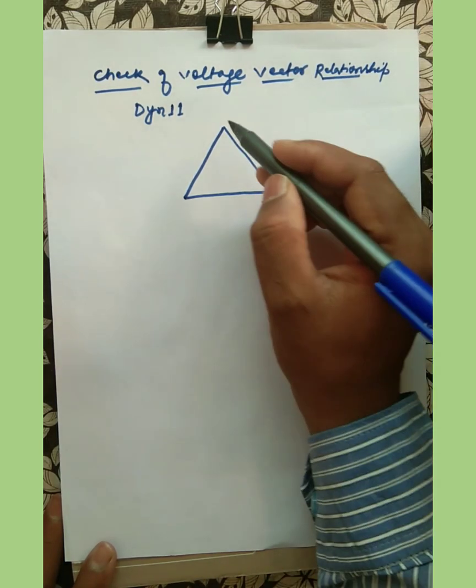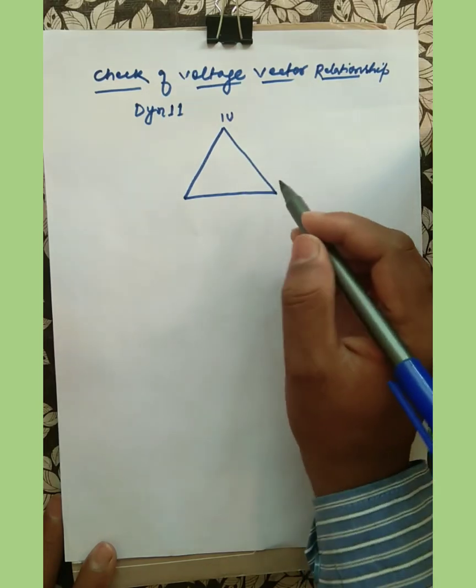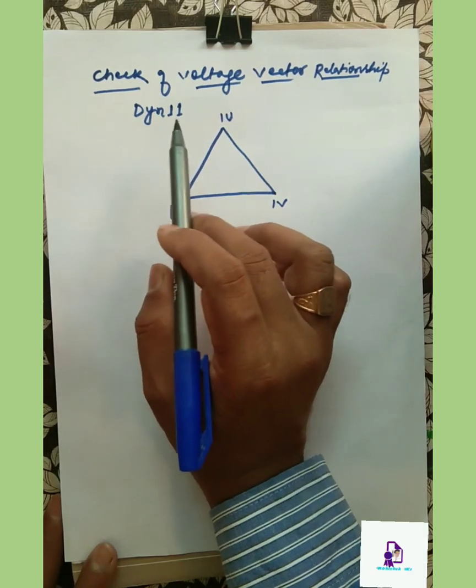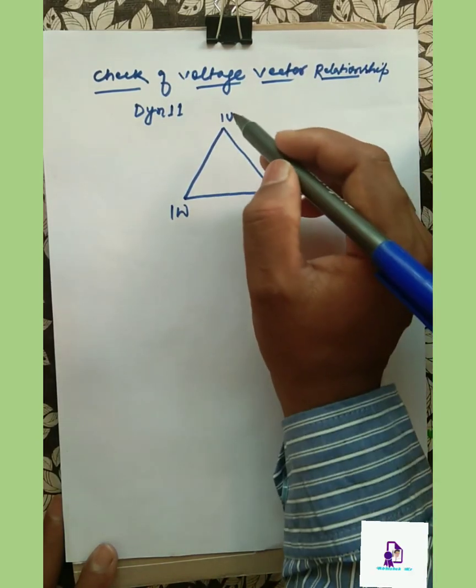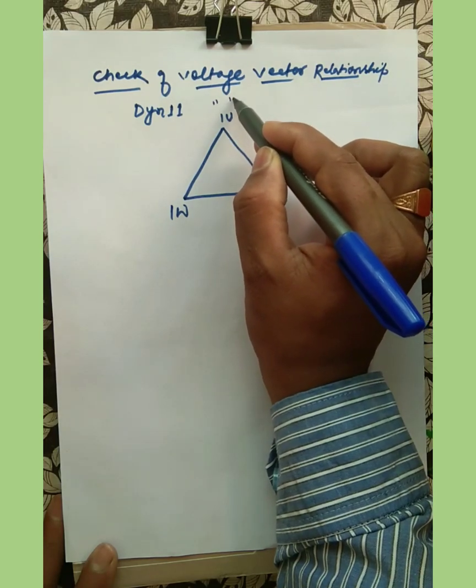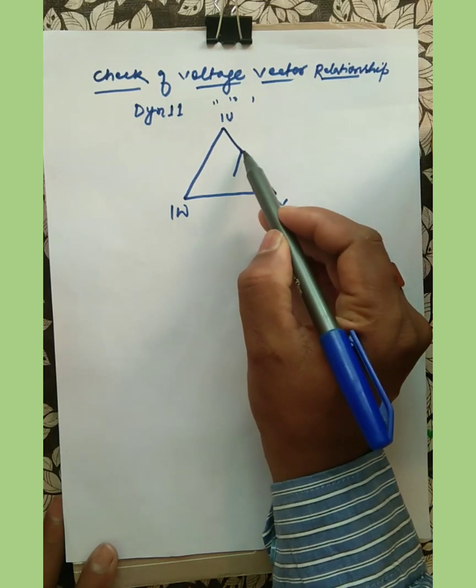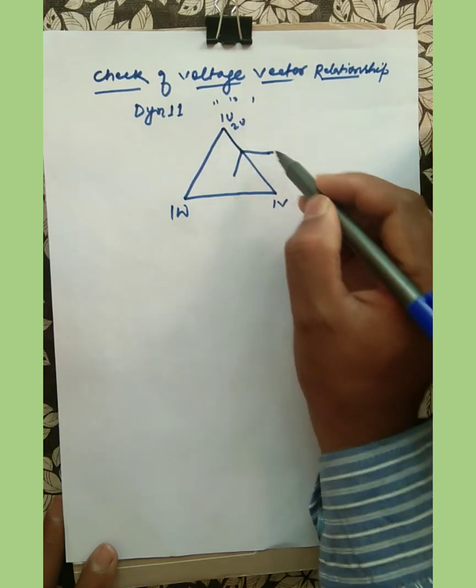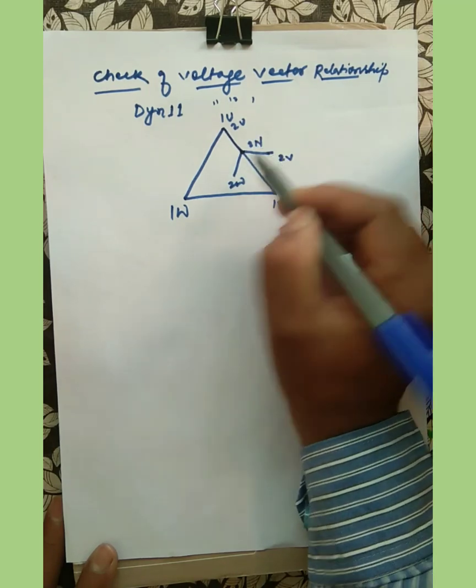This is the delta winding and we will write the notation as 1U, 1V, and 1W — this is the primary winding. We have a star connected secondary at an angle of 30 degrees, that is the 11 o'clock position. We notate the secondary as 2U, 2V, 2W, and 2N in anti-clockwise direction. '2' denotes the secondary side voltage and '1' denotes the primary side voltage.